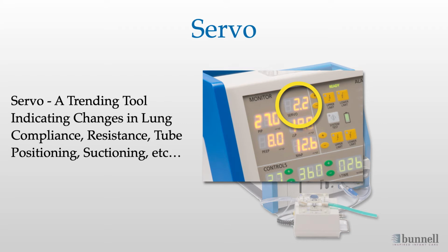A decrease from the baseline value or a low servo alarm may indicate the need for suctioning, poor tracheal tube position, or decreased compliance. Less flow is being used to maintain the set jet peak inspiratory pressure, therefore less tidal volume is being delivered. A patient assessment should be made to determine the cause.